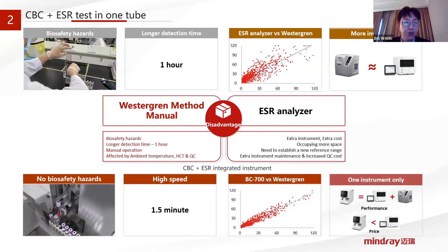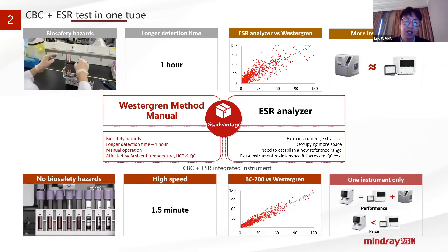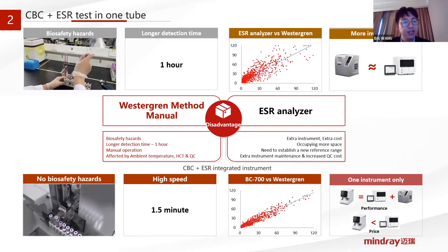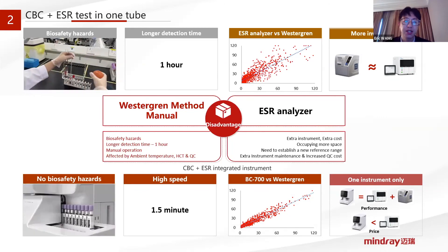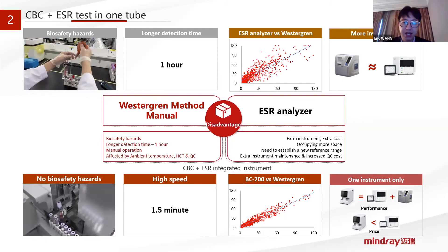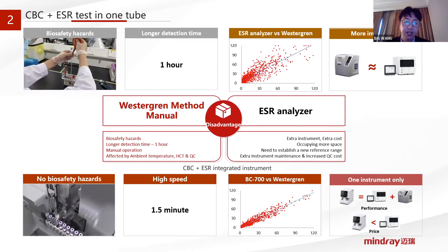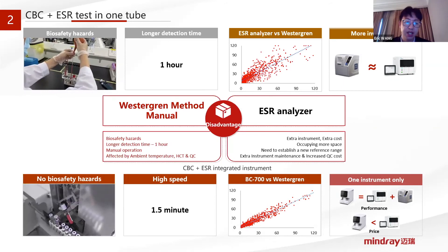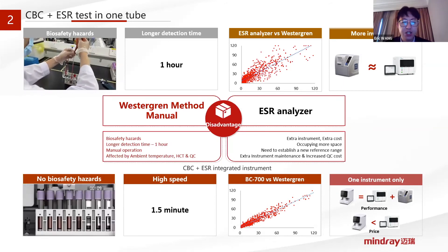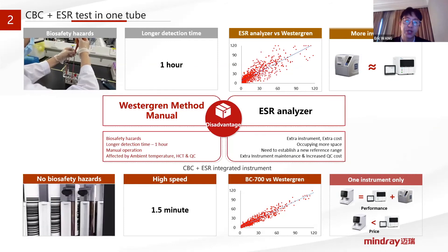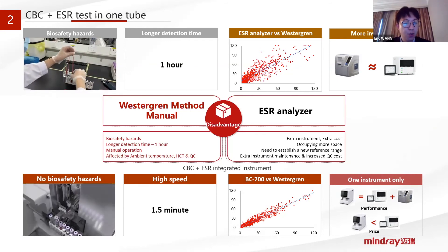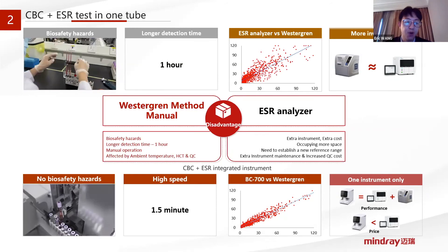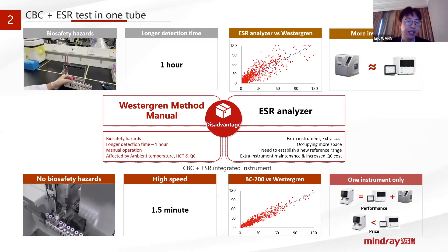Now the BC700 series offers you an all-in-one solution. We can use less blood from patients — especially for pediatric and other patients — only around 150 microliters. Additionally, technicians do not have to wait an hour for results. It only takes one and a half minutes to get results for both CBC and ESR tests in one run.